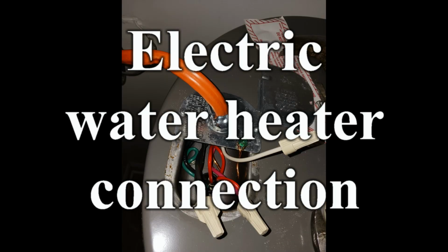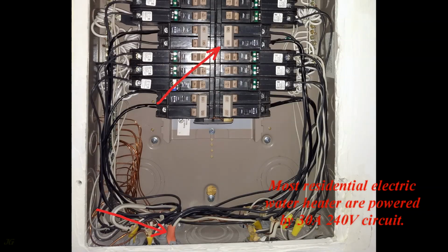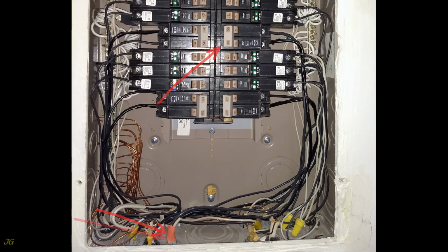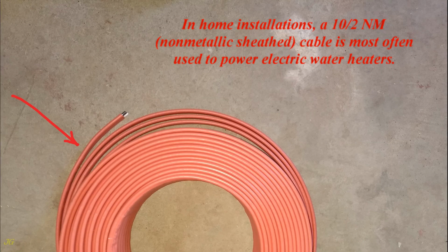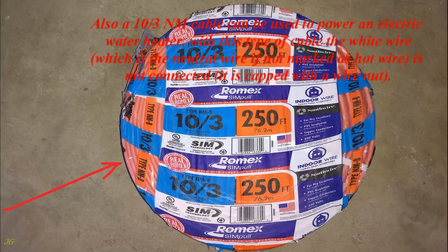Electric water heater connection. Most residential electric water heaters are powered by a 30 amp, 240 volt circuit. This circuit requires 10-gauge wire. In home installations, a 10-2 NM, non-metallic sheathed cable is most often used to power electric water heaters. Also, a 10-3 NM cable can be used to power an electric water heater.